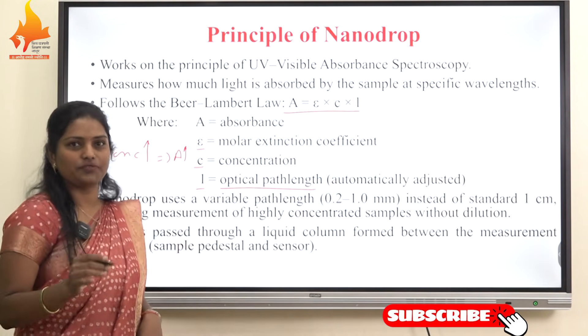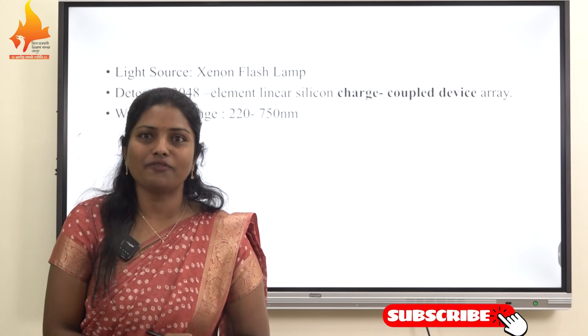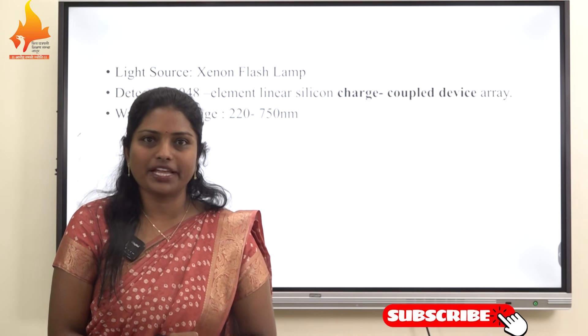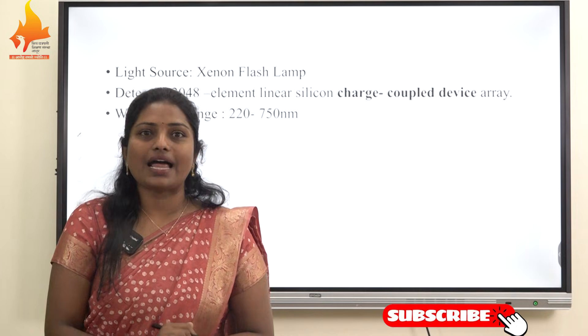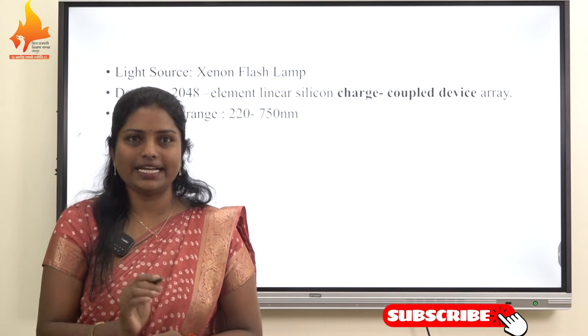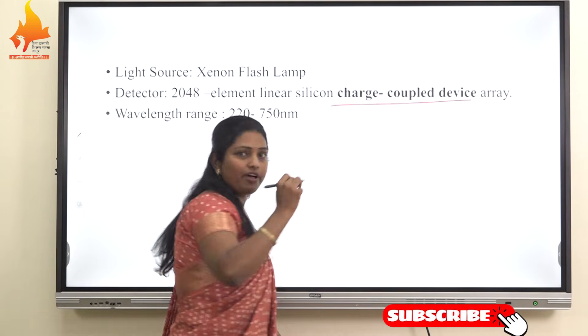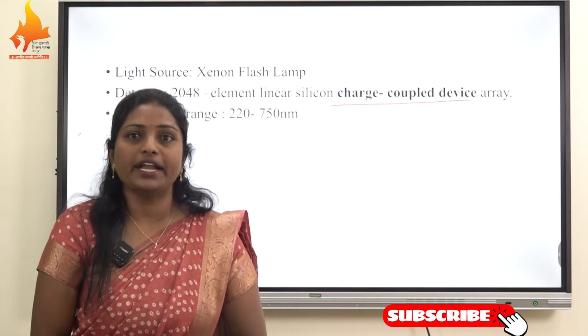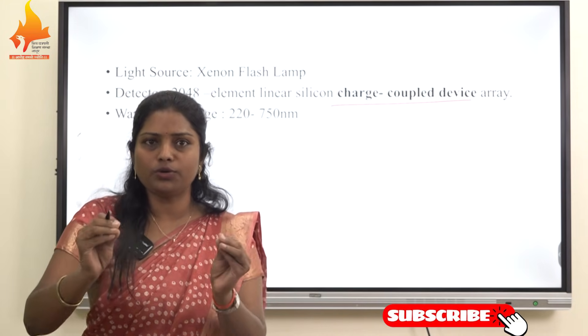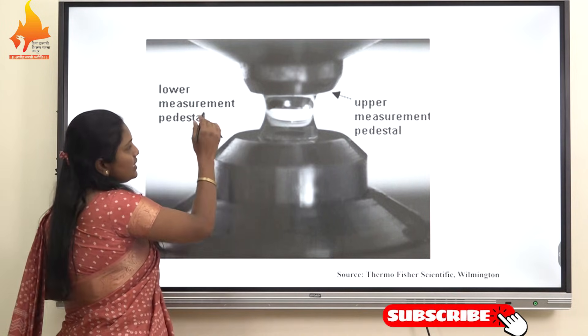The nanodrop instrument uses a pulsed xenon flash lamp as a light source, which emits high-intensity light across the UV-visible range in a single flash. The transmitted light is detected by a 2048-element linear CCD — charge-coupled device — array detector, enabling rapid full-spectrum analysis from 220 to 750 nanometers.